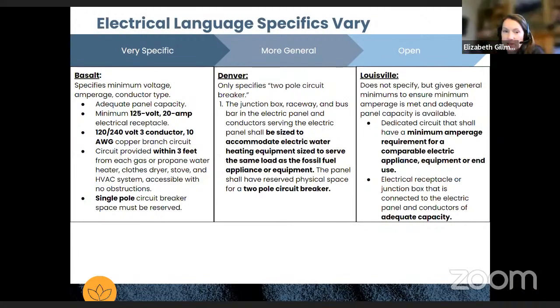This is a really hard question because there's no plug-and-play option. I can't just say, well, you're going to provide the heat pump version of that furnace. That doesn't exist, so it's not something we can size and say here it is. It's a 2-pole, it's a single pole, you need this much wire. We don't even have the equipment. We're designing for something that doesn't exist, or we're trying to prepare homes for equipment we can't buy today because it's not out there. So it's a really hard problem for a number of reasons.